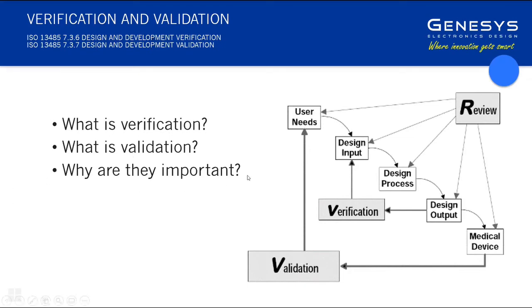Okay. Well, tell us why they're important. Well, I think the fact that they're called up by the regulatory standards is probably enough, but they also are extremely important in their own right if you want to develop a product that will be accepted by the marketplace. You could easily come up with a product that meets all of the requirements of ISO 13485 that the users won't use because they don't like the way it operates. So they're important from a much broader perspective than just regulatory compliance.